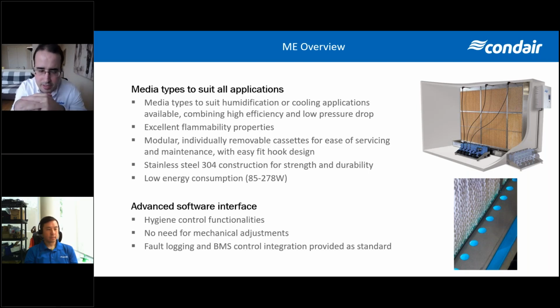Also, our system has very low energy consumption, like I said before, less than 300 watts. It's all stainless steel: the tank, the uprights, the cassettes. All the metal in the system is stainless steel. The hydraulic modules can be installed inside or outside your duct, as you can see in the picture. We also have different hygiene features like drain cycles, submerged UV on the tanks, and inline UVs. All the blue mold you can see in the hydraulic module is also antimicrobial plastic. We implemented these hygiene features to avoid the risk of biofilm development during the application.